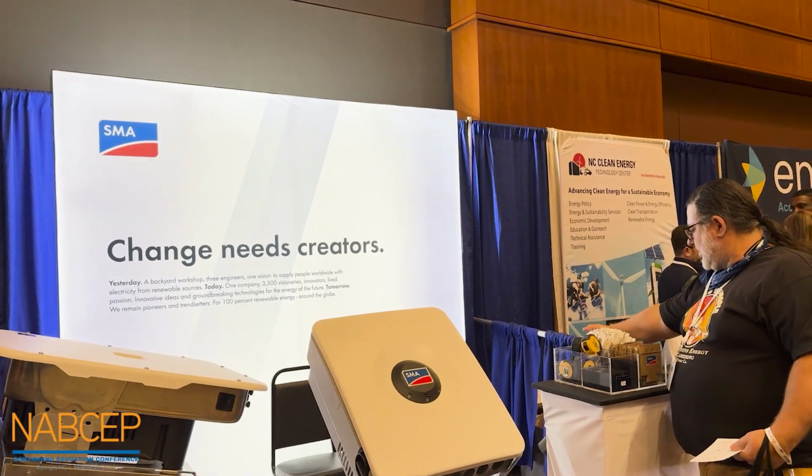Are all transformers oil-based transformers? No, there are dry type transformers. Okay. And for dry type transformers, you also do turns ratio, you also do winding resistance, but instead of the power factor test, which is an insulation test, you preferably do an insulation resistance test. Okay. So let's go back to this insulation resistance test, aka meggering something. Why would someone need or want to do an insulation resistance test, or megger a line? And where is this test done in a typical solar array?